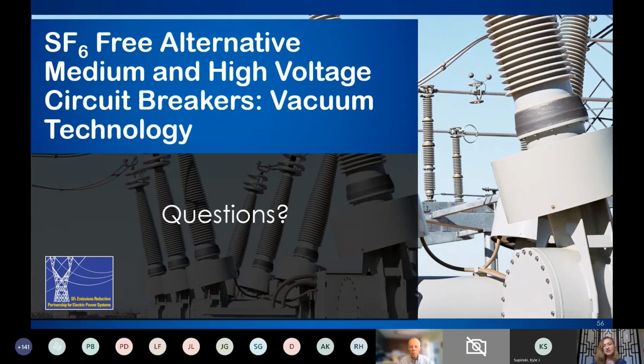I think that's going to come my way. Okay, well, first of all, shunt reactors and shunt capacitors are a small subset of the applications of breakers in the system. Most breakers are used for line protection and transformer protection. So currently our position right now is that we are not using vacuum breakers for those two types of applications, for shunt reactors and capacitors. We are still using SF6 at this point until further developments can be made, or other technical changes that would permit us to use them for reactors and capacitors.